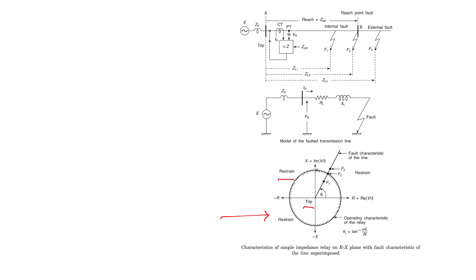So it is obvious that the tripping characteristics of the distance relay to protect the entire length of the transmission line should actually be a small area. This is the tripping area, a small area on the RX plane which contains the fault characteristics of the transmission line. Unfortunately, the tripping characteristics of the simple impedance relay is too large an area in the RX plane than ideally required. This is an undesirable trait because it gives rise to maloperations of the relay. So we have a large tripping area, and this is one of the disadvantages of this type of relay.